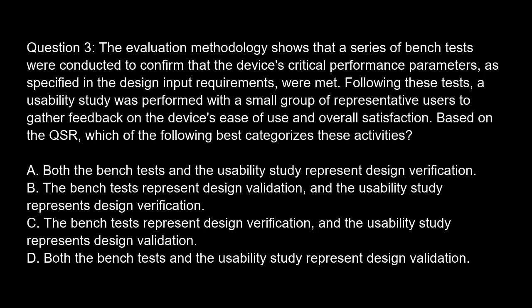Question 3. The evaluation methodology shows that a series of bench tests were conducted to confirm that the device's critical performance parameters, as specified in the design input requirements, were met. Following these tests, a usability study was performed with a small group of representative users to gather feedback on the device's ease of use and overall satisfaction. Based on the QSR, which of the following best categorizes these activities?